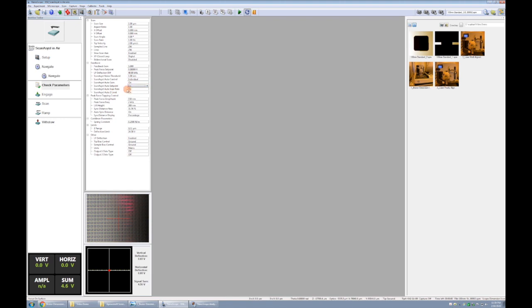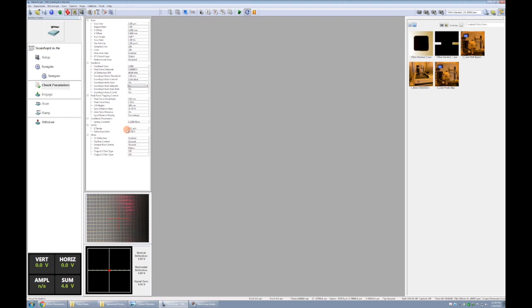We'll skip these two, and then we have auto scan rate. We can leave that on. If it senses that the tip velocity is too fast for the size of the features that are being scanned, it will lower the scan rate and therefore decrease the tip velocity. Auto z limit, we turn that on if we want the software to automatically adjust the z range. This is how we can adjust the z resolution that is achievable. To know the z resolution, we take the z range and we divide it by 2 to the 16th power for our 16-bit DAC. We're able to improve the z resolution by an order of magnitude by taking it from 12 down to about 1 or 2 microns if we're only scanning samples that have very shallow features.